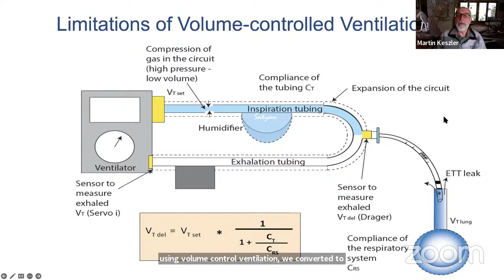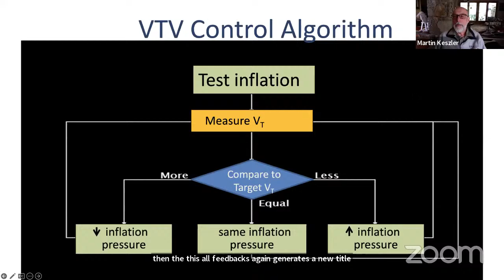So the basic approach to volume targeted ventilation, and again, the distinction is that volume targeted ventilation, things like volume guarantee, are actually pressure controlled ventilation with continuous real-time adjustment of inflation pressure. So there is a pressure that's generated. The tidal volume that results from that is measured and is compared to the target tidal volume. And then depending on whether that measured tidal volume is less than, equal to, or greater than the target, the inflation pressure will be adjusted upward, kept the same, or reduced for the next cycle. And then this all feeds back again, generates a new tidal volume, and the cycle repeats. So that's the basic way this works.